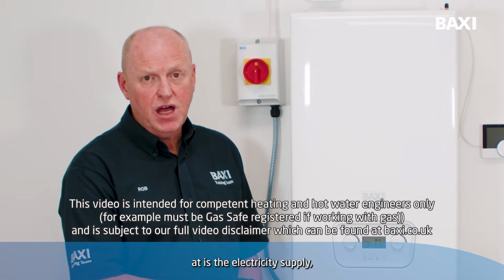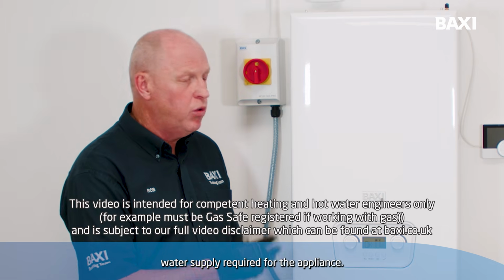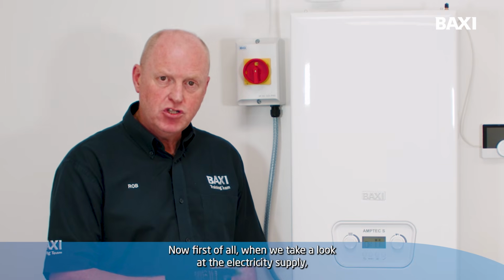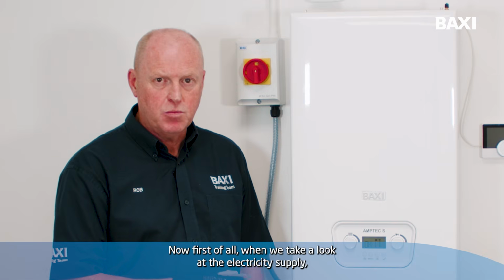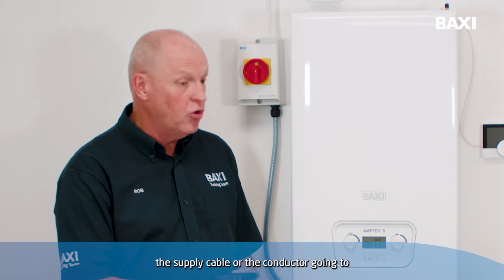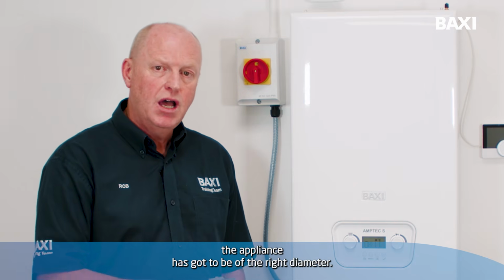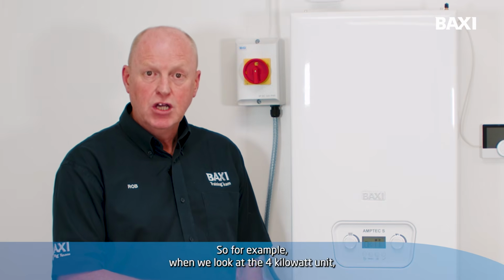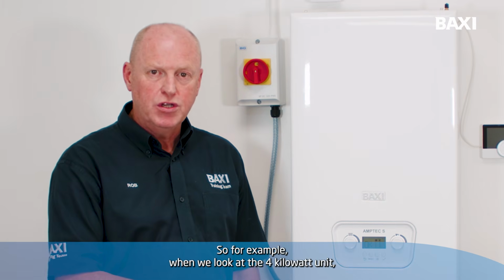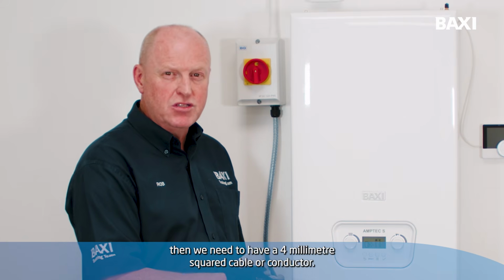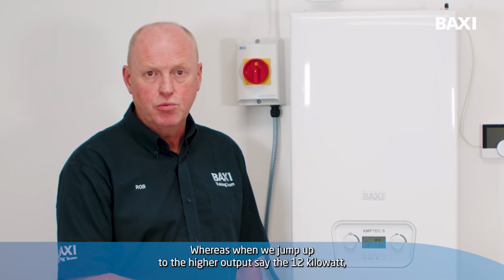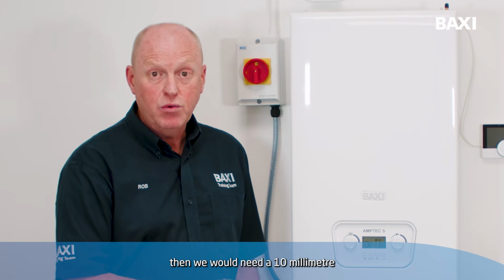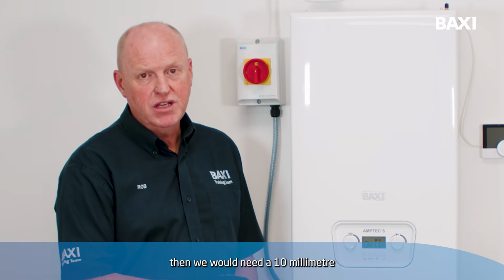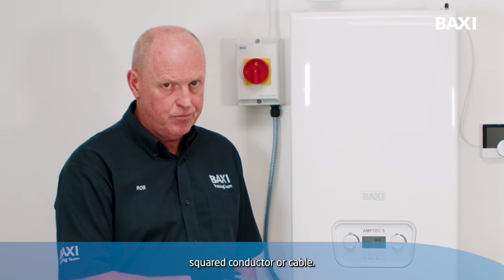So what we're going to take a look at is the electricity supply and water supply required for the appliance. Now, first of all, when we take a look at the electricity supply, the supply cable or the conductor going to the appliance has got to be of the right diameter. So for example, when we look at the 4 kilowatt unit, then we need to have a 4mm squared cable or conductor. Whereas when we jump up to the higher output, say the 12 kilowatt, then we would need a 10mm squared conductor or cable.